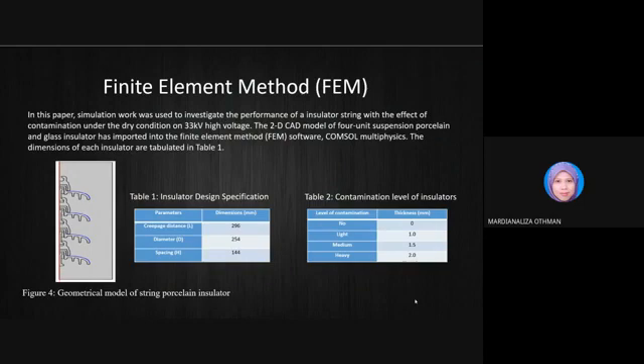For the methodology, in this paper, simulation work was used to investigate the performance of the insulator string with the effect of contamination under dry condition on 33 kV high voltage. The 2D CAD model of the 4-unit suspension porcelain and glass insulator was imported into the finite element method software, which is COMSOL Multiphysics. The dimensions of each insulator are tabulated in Table 1.